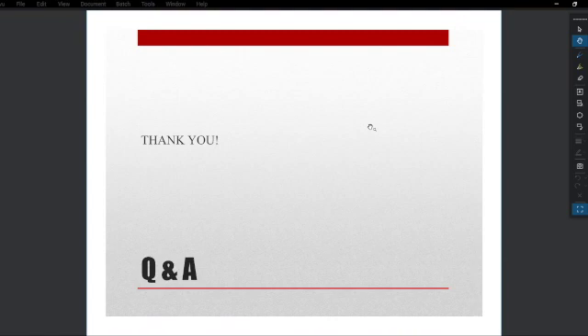Skipping down to Valerie: did you experience any issues or complications while going through the permitting process? Short answer, no, because I don't think there's anything different with passive house projects and permitting in any way. One thing that comes to mind is the CCD-1 that Tommy briefly touched on for unitized ERVs, there's a mechanical code requirement to be a minimum of 10 feet away from any intake for an exhaust. If you use a unitized ERV system, it's hard to meet that requirement floor to floor, even alternating supply and exhaust on different floors. In cases like that you may need a CCD-1 approved by the city allowing less than the 10-foot requirement. We had this happen on the Morris 2 project, for example. I can't think of anything else off the top of my head that would affect the permitting process.